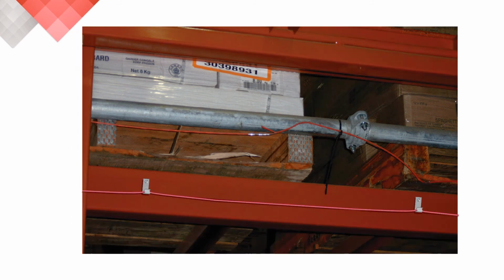We use this slide to highlight now how and where we would recommend putting the Protectowire. We recommend the longitudinal flue space on the back of the horizontal load beam, so it's better protected from pallets in the racks and from falling objects in the flue space, with a lower profile closer to the load beam.